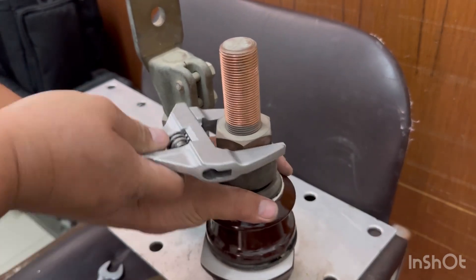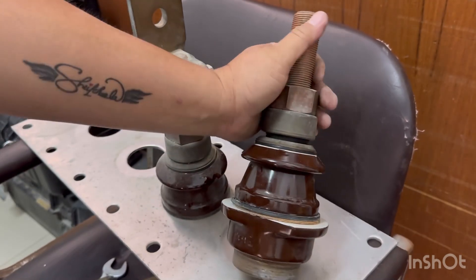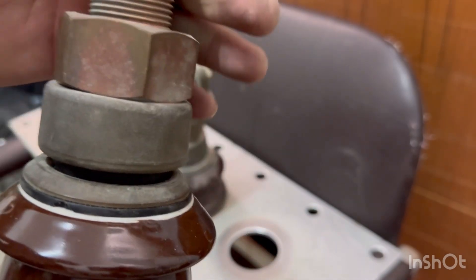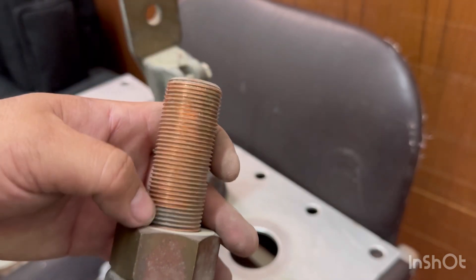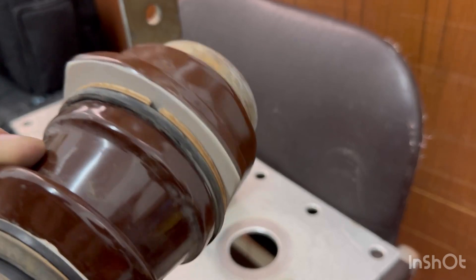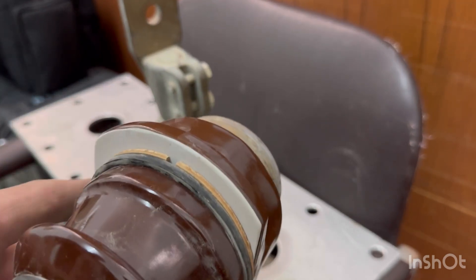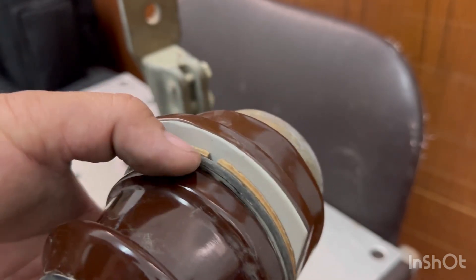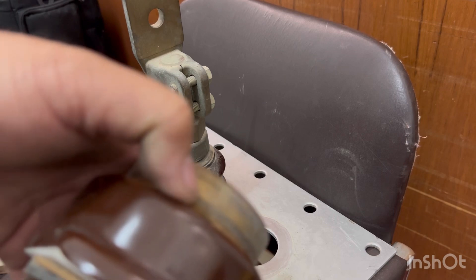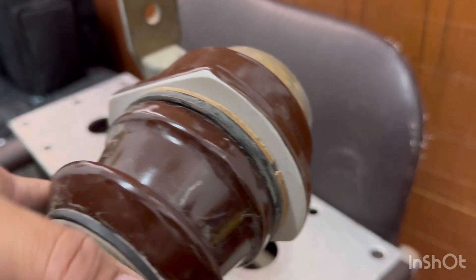Should we make it tighten — like that. This one here will be compressed, lacking the space between the spacer and the terminal, so that oil will not come off. The purpose of this hole is that it should be at the top, because the oil will go inside and air can also go out — filling the inside of this bushing with oil. So the air gap inside will be completely filled, and this section will be completely filled with oil.